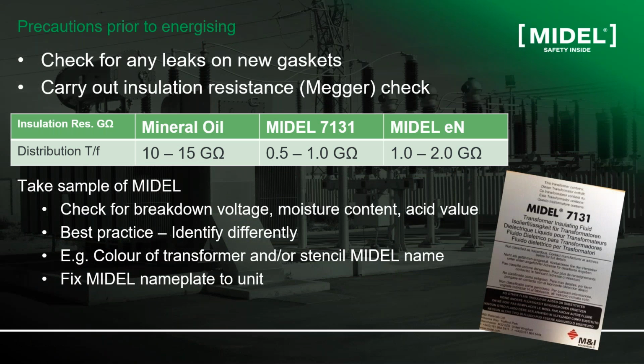Now, of course, as we are doing this, we may observe leaks or remove gaskets. So better to use new gaskets as you are doing the job. It's better to fit new gaskets to prevent any further leaks. And of course, some utilities will measure insulation resistance, a megger test. It's worth mentioning here that esters have a different chemical structure than mineral oil, so the insulation resistance will naturally be lower for an ester-filled transformer compared to mineral oil.